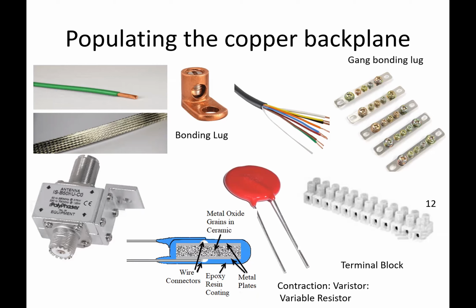The way they work is a metal oxide varistor is a variable resistor. It conducts voltage to ground beyond a certain voltage. This particular limit is 130 volts. The red one you see in my slide is rated for 130 volts, meaning anything above that gets conducted to ground. A lightning strike would probably be well above 130 volts, and the MOV would do its best job trying to conduct all that voltage and current to ground. It's going to get destroyed in the process, but probably save a human life in the meantime.